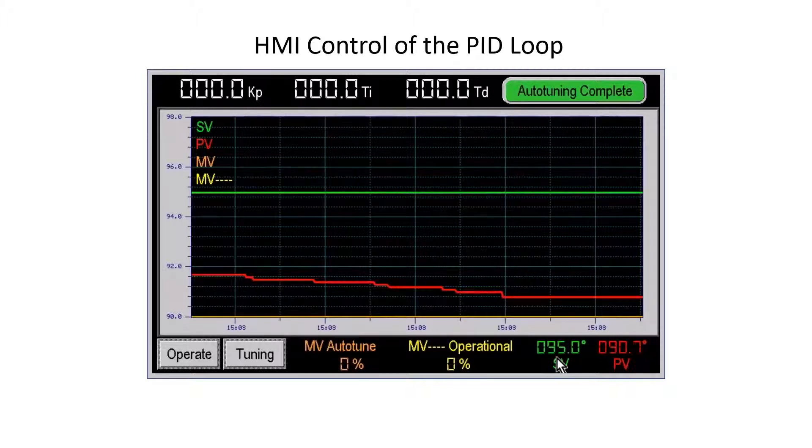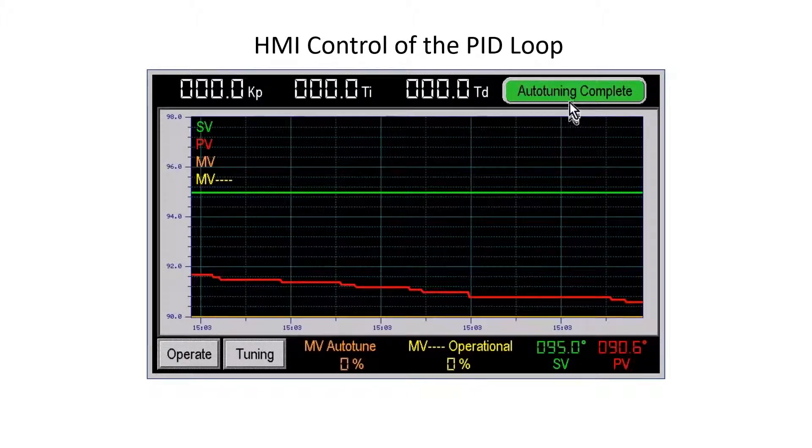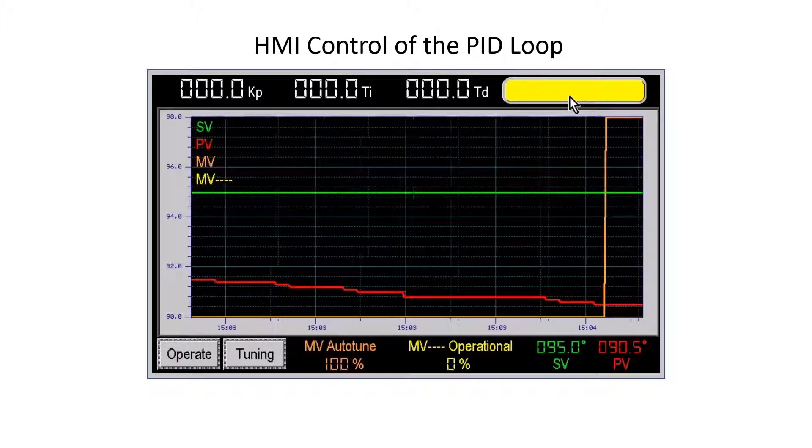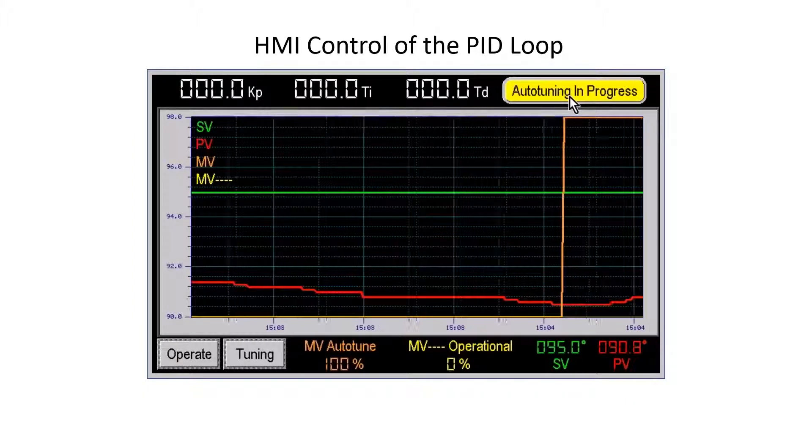Select a tuning SV near the normal operating value. In this case, 95 degrees. If the auto-tune button displays auto-tuning complete, the PID loop is ready for auto-tuning. Press the auto-tuning button to start the auto-tune routine.